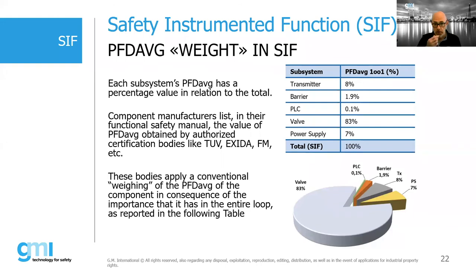Thank you. In the following slide, we see what weight the individual subsystems have within a SIF. It's important that every single component of a SIF, including the power supply system, is included in the PFD AVG calculation to achieve the required safety level. Every single element has its own percentage weight, which must be considered.